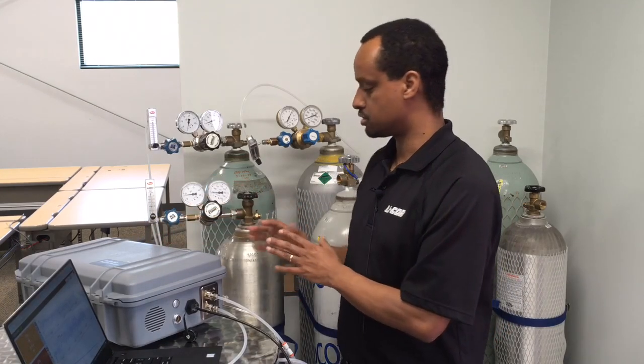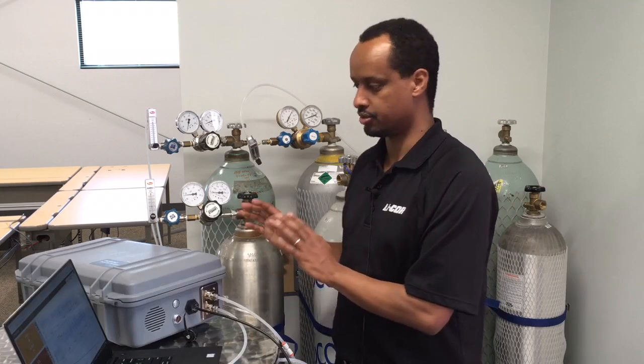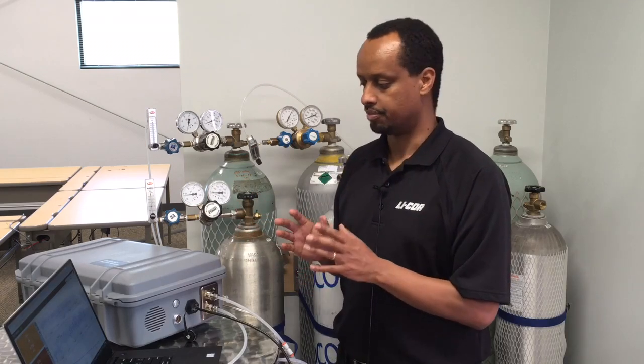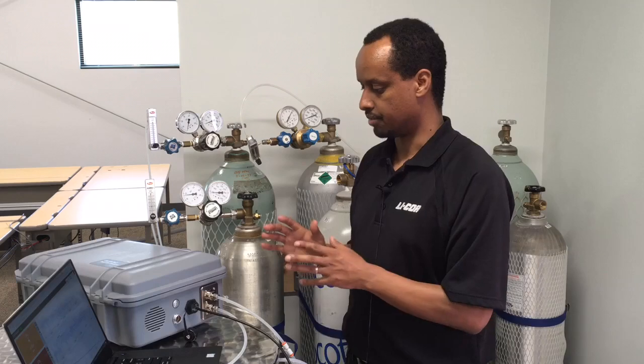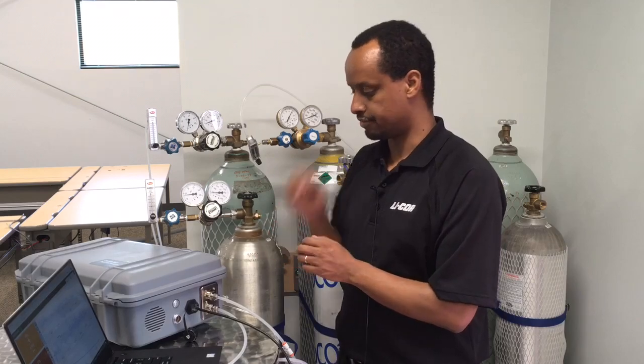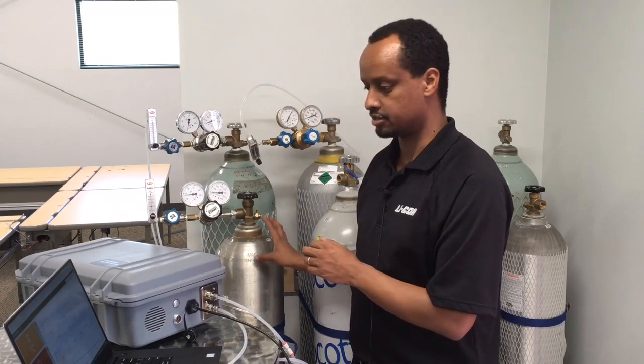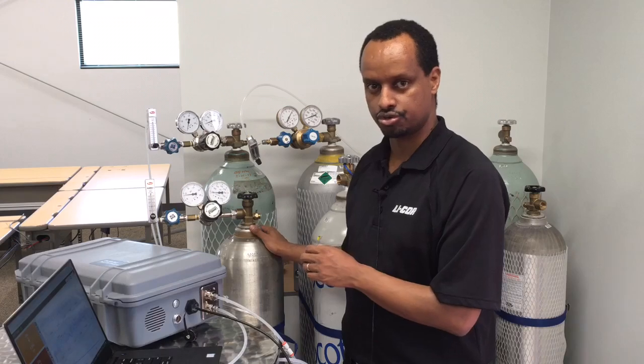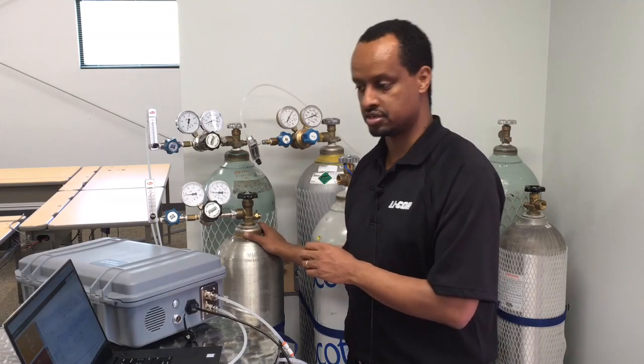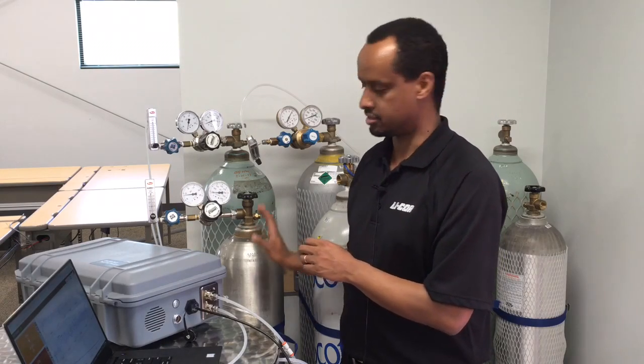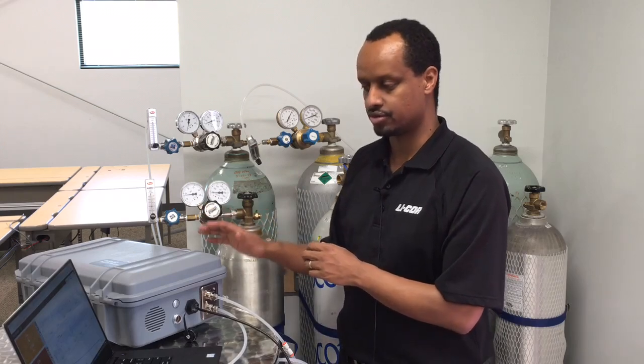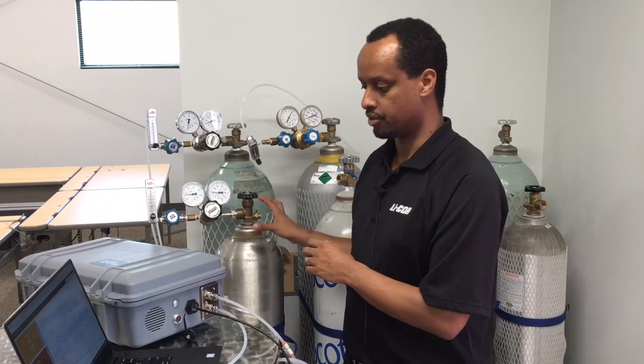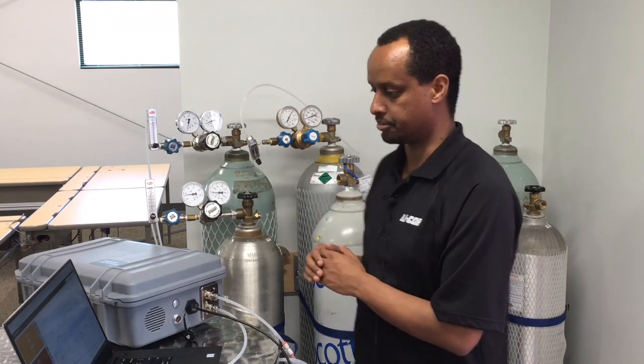So we suggest taking several minutes; the zero or baseline calibration is going to take a while. So when you do this baseline calibration or span calibration, you want to make sure you have enough time and you don't rush through it, because the calibration is going to be applied for all the measurements that you take subsequently. So you want to do it carefully and use reliable standards, and make sure you're not using nitrogen or methane mixed in nitrogen or nitrogen balanced tanks. The instrument is designed to work in measurements of air, so you want to use methane in air or air balanced tanks for doing the calibration.